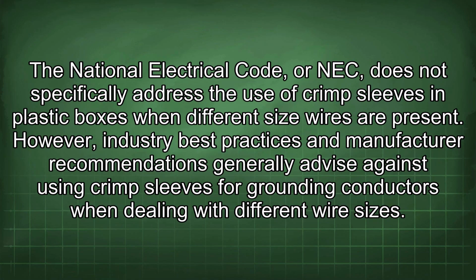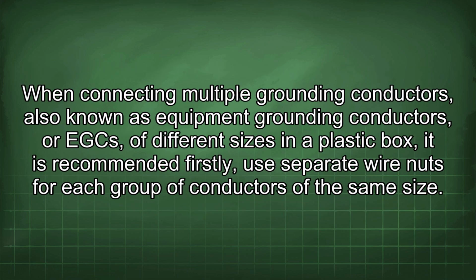National Electrical Code, or NEC, does not specifically address the use of crimp sleeves in plastic boxes when different size wires are present. However, industry best practices and manufacturer recommendations generally advise against using crimp sleeves for grounding conductors when dealing with different wire sizes.